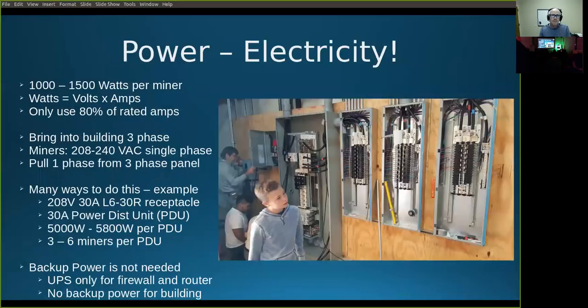Okay, power - that's a big one you're going to need. Here was the initial power build-out. Right in front of my son Grant there's a big 1200 amp circuit breaker. Big power comes in through a 500 kVA transformer, three phase, which is then broken down into three 400 amp panels. You can see three cables go into each of those panels, and then single phase is pulled off those.